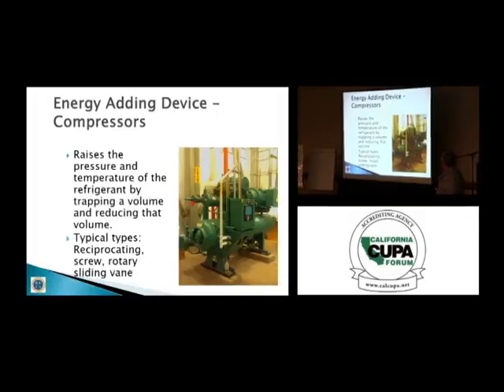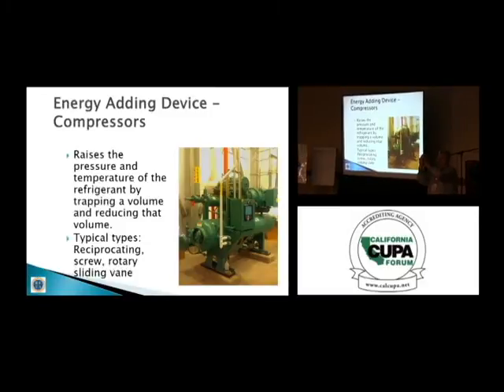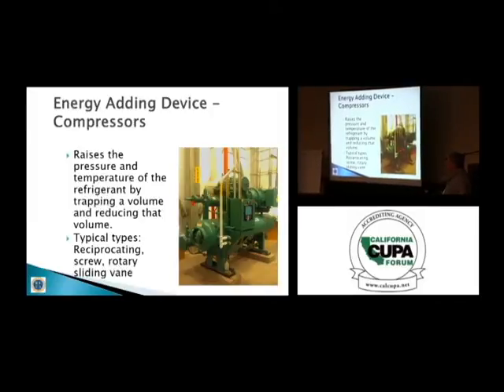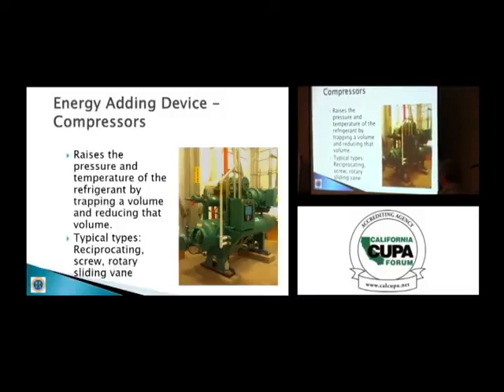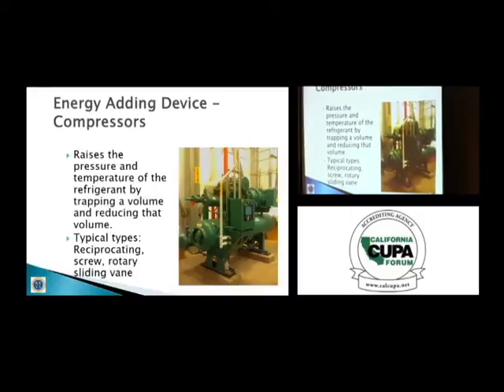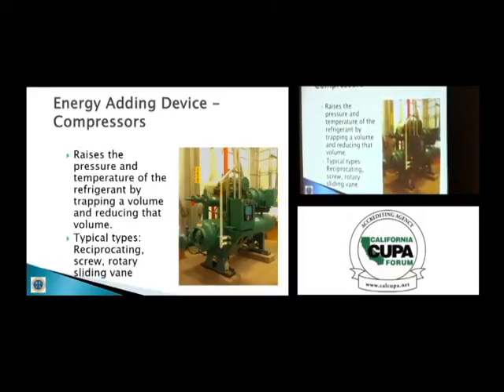Right about here, there's a barrier, a bulkhead. And on this side here, this is the side that takes the gas stream from the compressor. This particular size unit might be shoving out 1,200 cubic feet per minute into this dead end, and that's by design. It comes to the barrier, and then it has to squeeze itself through these coalescing filters. The coalescing filters wring out the oil, and it drops to the bottom here, and then there's a system to bring the oil back into the storage side of this separator.